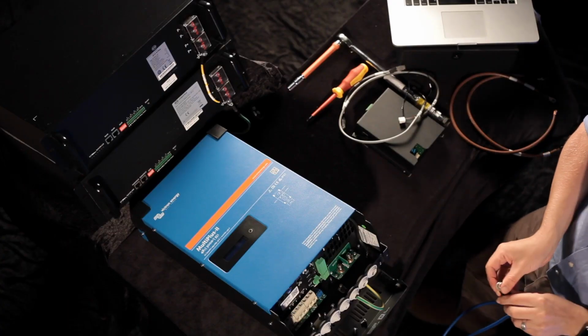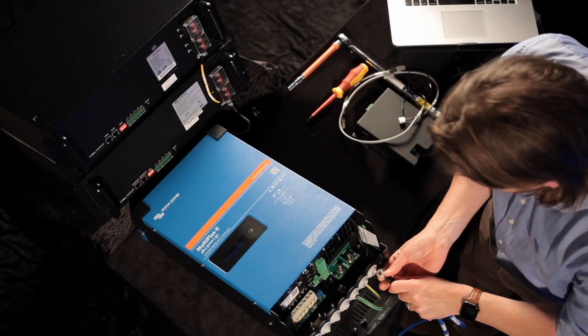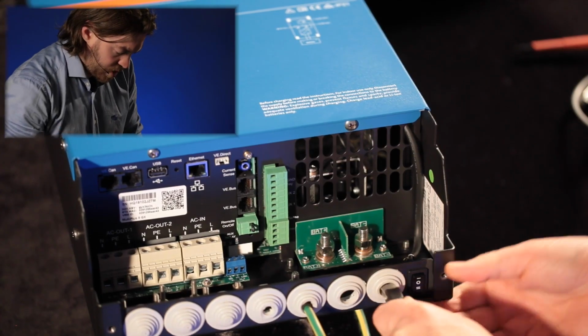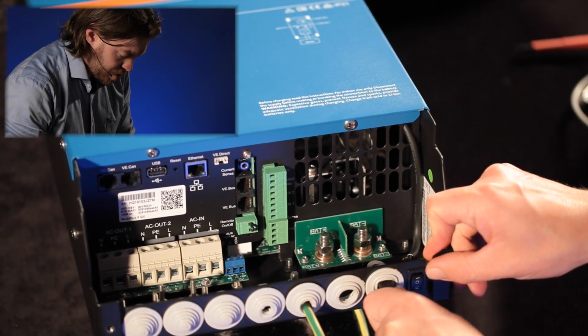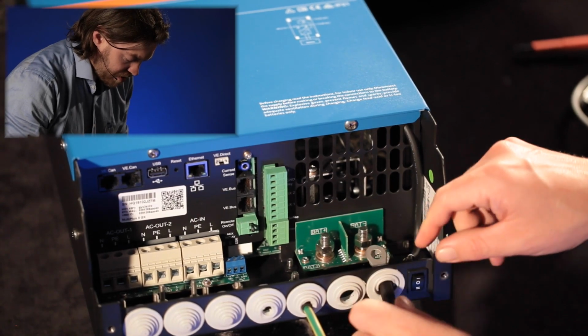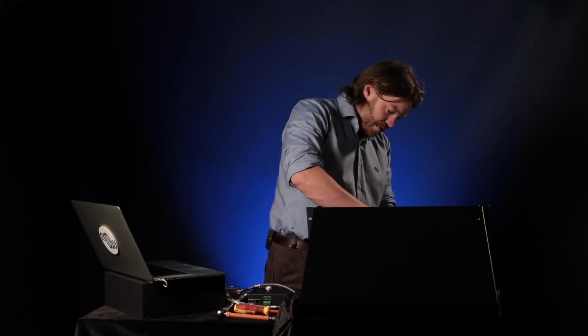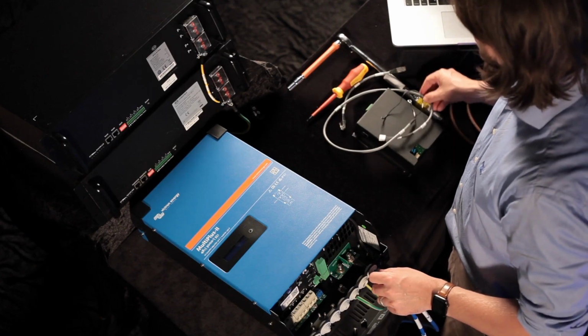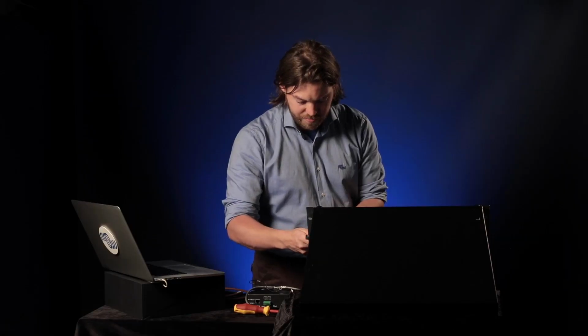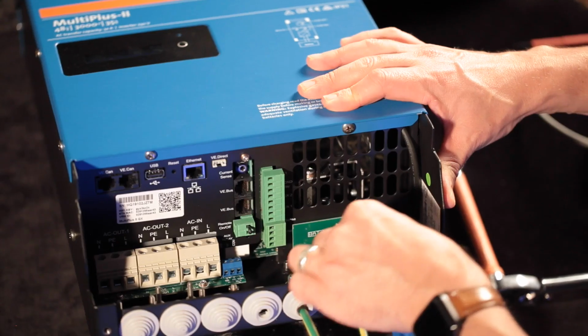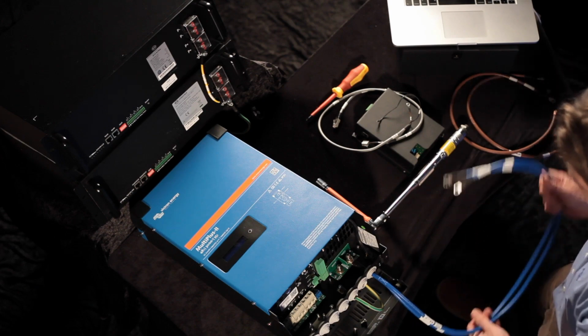I have enlarged the gland at the bottom here. I can now insert the 2 battery negative cables, tighten it up to finger tight, and then take your torque wrench, calibrated to 14 Newton meters. Everything looks secure. We can now bring these cables around.